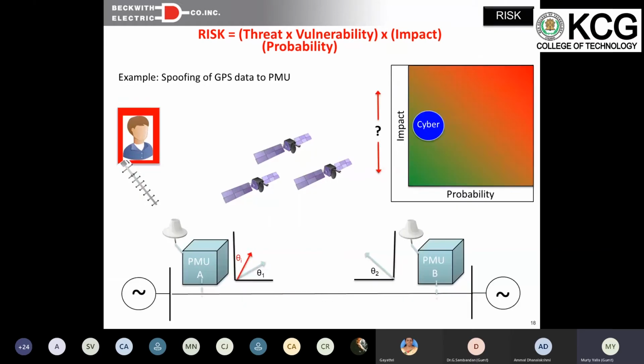This is GPS spoofing. If you're using PMUs, global positioning satellites send time sync signals. But if a hacker is nearby, near a substation or power plant, sitting outside in a car, and sends a stronger signal than the regular GPS, the PMU gets new coordinates. The sampling is then done differently, so it looks like there's a 50-degree phase angle between the two ends of the transmission line. It thinks there's an imminent problem, opens the breaker, and causes a blackout. So that is possible by hackers.